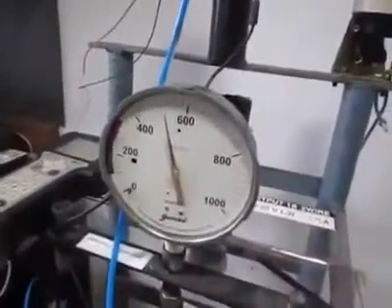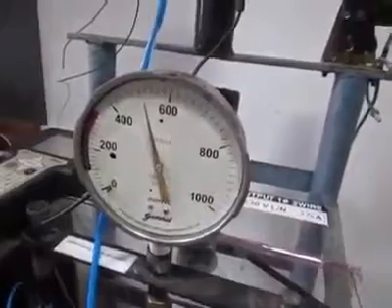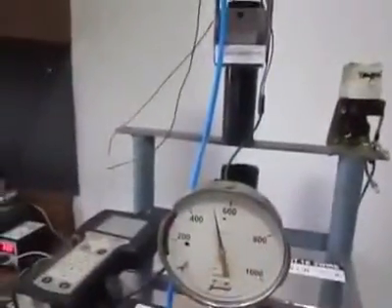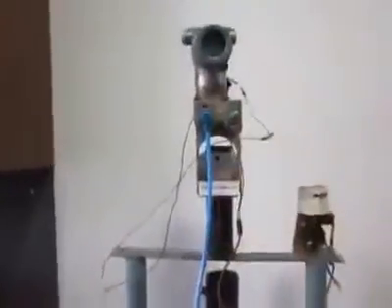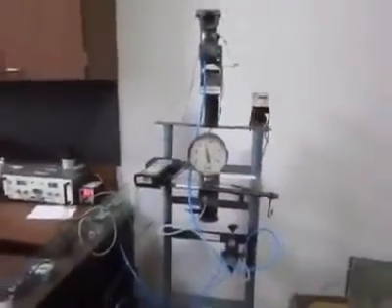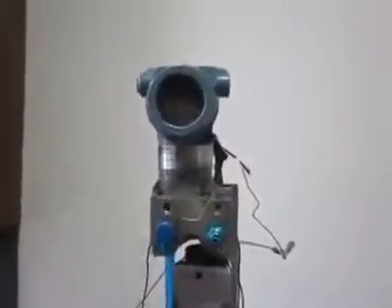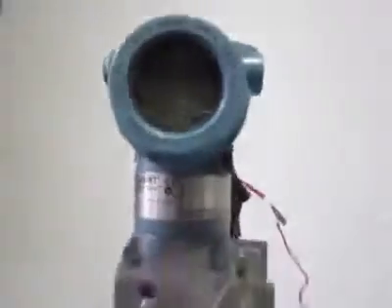Now this is decreasing slowly. The master pressure gauge is also at 500 mm of WC, a little bit higher, not too worried. And the process value I am seeing here is 12.1 milliamps. Like this I am gradually increasing, and again I will gradually decrease the pressure. I repeat the whole process 2 to 3 times, to get the accuracy and repeatable, fine values of the transmitter.